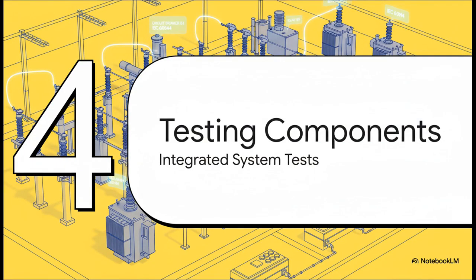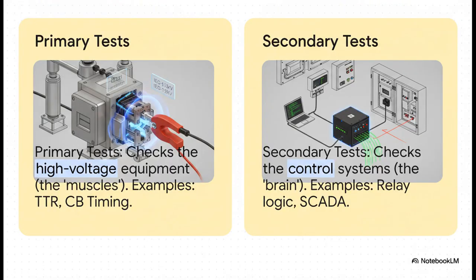Okay, with all the physical checks done, we move into the electrical testing. This is where we start using specialized test equipment to energize individual circuits. We're not just validating that each device works, but more importantly, we're making sure they all work together as one single integrated system. A great way to think about this is muscles versus the nervous system. The primary tests on the left check the high voltage muscles to make sure they can handle the power. The secondary tests on the right are all about the nervous system, the protection relays and control logic. We're making sure the brain is giving the right commands at exactly the right time.